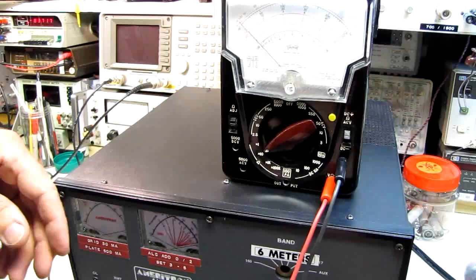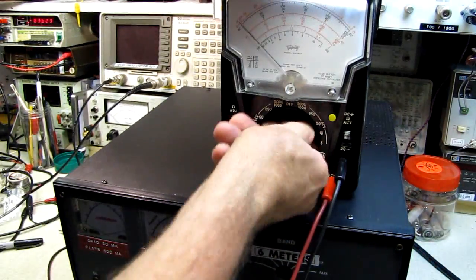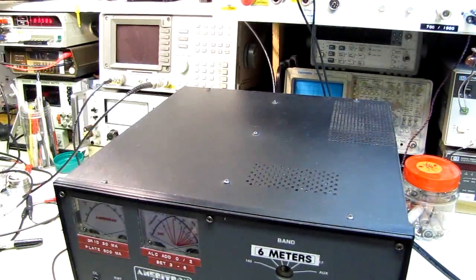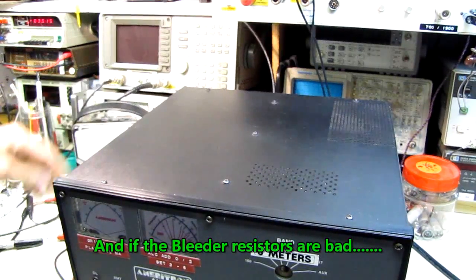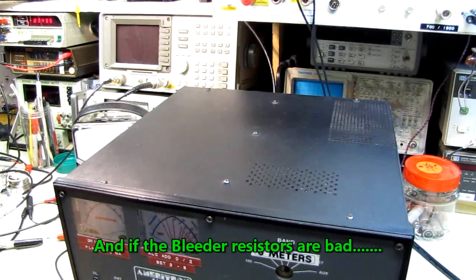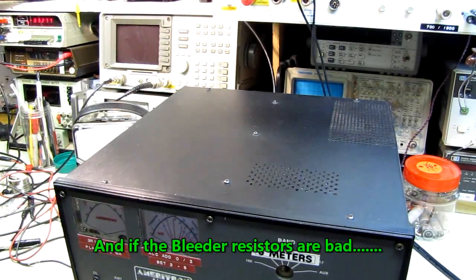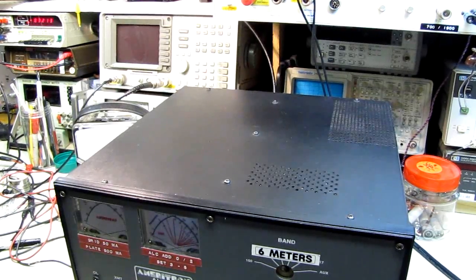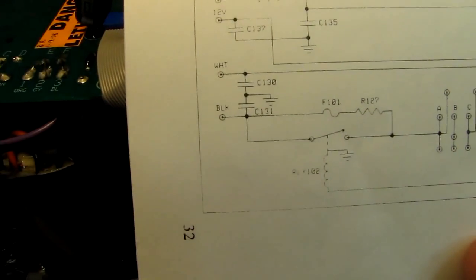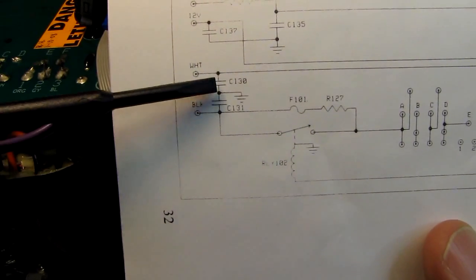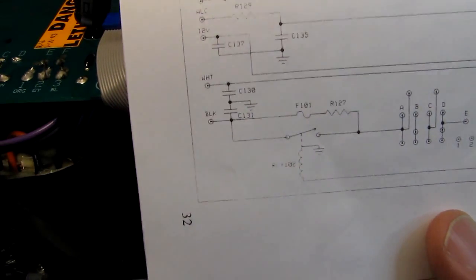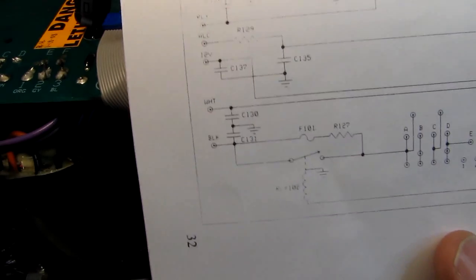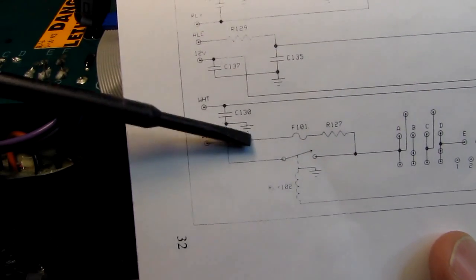We'll get the chicken stick out and make sure the capacitors are discharged. And remember, these caps, if the conditions are dry, if the humidity's low, these caps can hold a charge for days. So you don't want to be sticking your fingers in there. So we'll take the cover off and discharge the caps and see if we can find the bad one. When I say caps, I mean the high voltage supply caps. All right, in our schematic, these two capacitors are labeled C130 and C131. Those are the two that I showed you are in a series configuration with the center grounded.